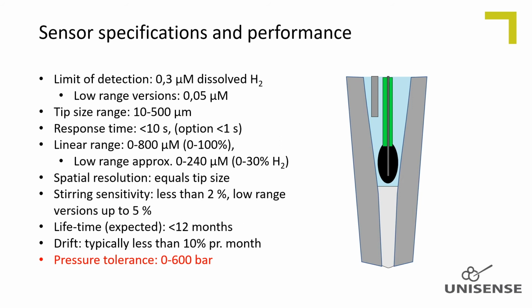The hydrogen sensors stand up to 5 times atmospheric pressure without being pressure compensated. However, like other Unisense microsensors and electrodes, we can pressure compensate the inner parts of the sensor, so they do withstand full oceanic pressure. When pressure compensated, they are tested to be able to withstand 600 bars.